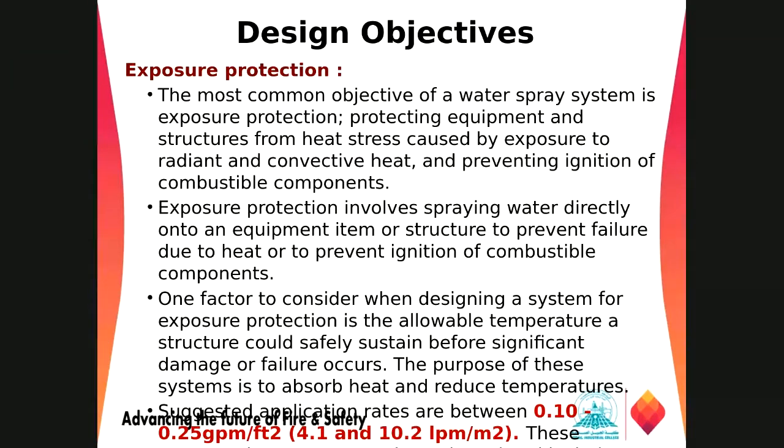The most common application of the water spray system is exposure protection, right? Just to cool the surface and reduce the temperature of those areas so that it cannot catch fire easily. Exposure protection requires spraying water directly onto the equipment or structure to prevent failure due to heat, right? As I mentioned, once the temperature goes higher, it will break easily, and at that time it will release flammable liquid or gas, which is not good for the plant, for the environment, or for society.